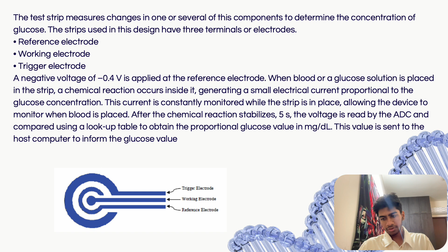Now, the electrical current produced by the enzymatic reaction is measured by the electrodes, which are embedded in the test strip itself. These electrodes are typically made of conductive materials such as gold or carbon. Now, the main process would be signal processing. The signal generated by the enzymatic reaction is very weak, so it needs to be amplified in some way and processed to obtain an accurate glucose measurement. The glucometer contains a microprocessor and electric circuitry for signal amplification, noise reduction, and calibration.